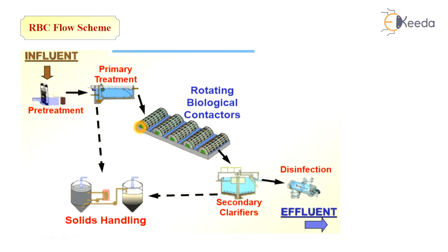The flow sheet of the rotating biological contactor is as follows. First, pretreatment is provided in terms of screening and a grit chamber. Then the effluent goes to primary treatment, that is the primary sedimentation or primary clarifier. The effluent from the primary clarifier then goes to the rotating biological contactor. As you can see in this diagram, a number of rotating biological discs are placed in each unit of tank, arranged in parallel, and are continuously rotating. The effluent from the RBCs then goes into the secondary clarifier, where settled sludge is passed to solids handling devices or a sludge digestion tank.